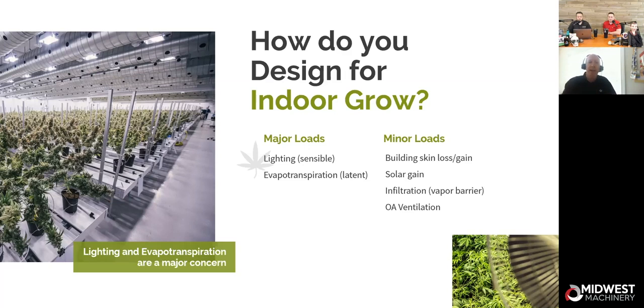So the lighting load is your sensible cooling load. All those lights, whether they're LED or HID, they're putting off heat energy. A watt in equals a watt out. So however many watts are going into the room, that can be converted to BTU, and we can calculate how much light energy needs to be offset by some sort of sensible cooling machine. So that's a real easy one.